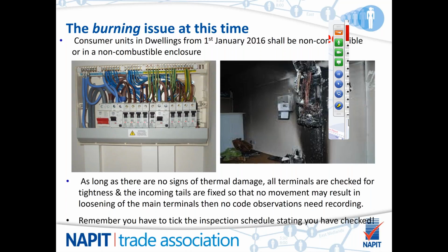So it is very, very important to make sure that when we're inspecting and testing our installations, all of those terminals are nice and tight, and that there is no visible sign of overheating or damage or burn marks in there. If everything looks nice and clean and put together well and everything's tight, then there's no need to give anything a code here. However, should you find that there has been some sort of arcing or some sort of burn marks, then there is need for some action. Don't forget the inspection schedule asks about your consumer units, distribution boards, and you would be ticking the inspection to state that you have checked it.